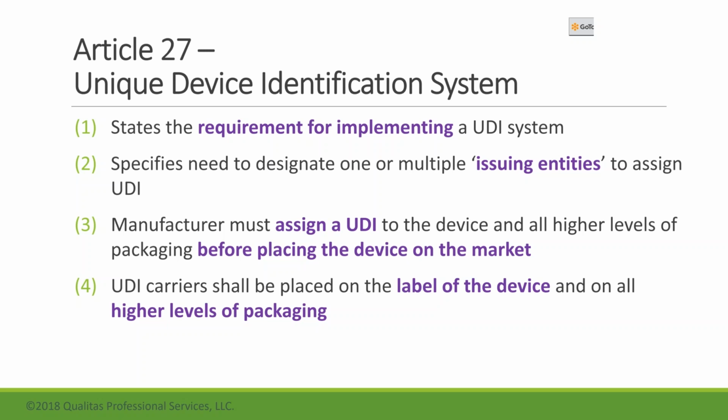It states very clearly that a manufacturer must assign the UDI to the device and all higher levels of packaging, and this is critical, before placing that device on the market. So we'll have to talk a little bit about logistics and timing, because what about products that are already on the market and so on. So we'll talk about that a little bit later on.